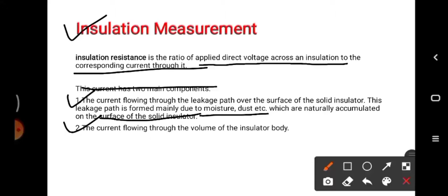Next point is methods of insulation resistance measurement. There are several methods. The first method is a direct indicating ohm meter with a hand driven DC generator, also known as a hand driven megger. The second method is a direct indicating ohm meter with a motor driven DC generator. The third method is a direct indicating ohm meter with a self contained battery. The fourth method is a direct indicating ohm meter with a self contained rectifier. And the last method is a resistance bridge circuit with self contained galvanometer and battery.